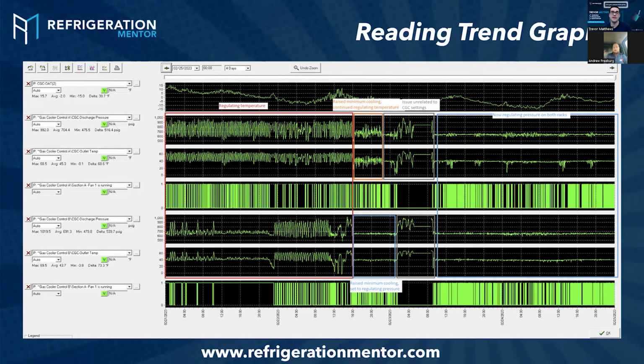This is an example on the screen right now, a trend graph for a CO2 system. Depending on what you want to look at will depend on what you want up there. This one is for the high pressure valve. So we got the outside air temperature, the discharge temperature, the outlet drop leg temperature, and whether the fan is running. This is all for the gas cooler.